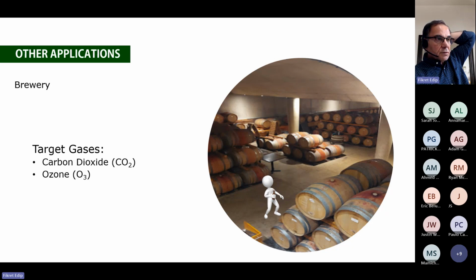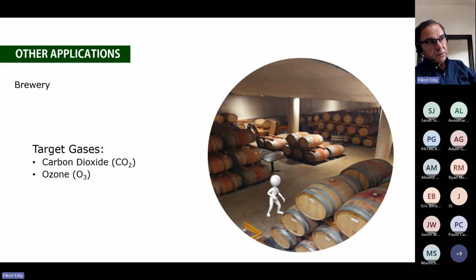For brewery, CO2 and ozone. Why do we put CO2 in there, and why do we put ozone? Mainly used for cleaning. Now, why are you putting CO2 in? Often if there are larger tanks of CO2, then you will need to put an oxygen sensor in there, because CO2 depletes oxygen. So we need to protect people from asphyxiant gas.